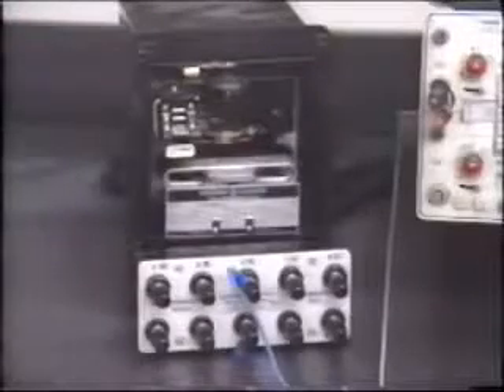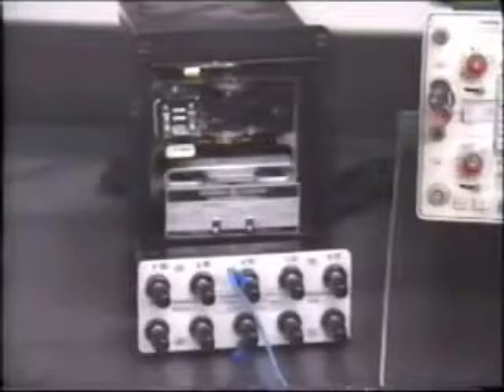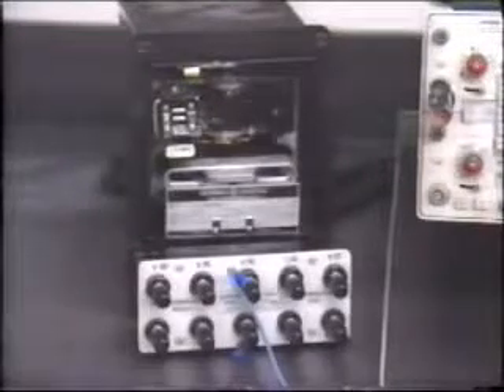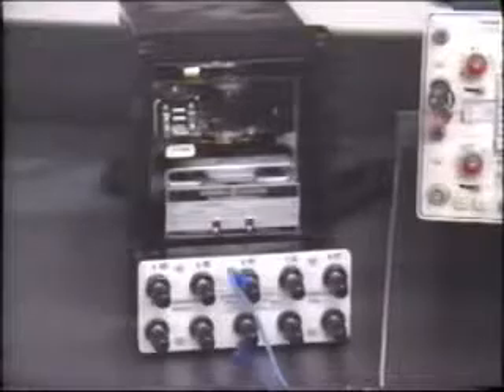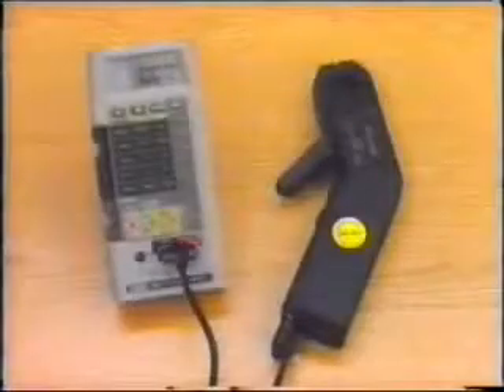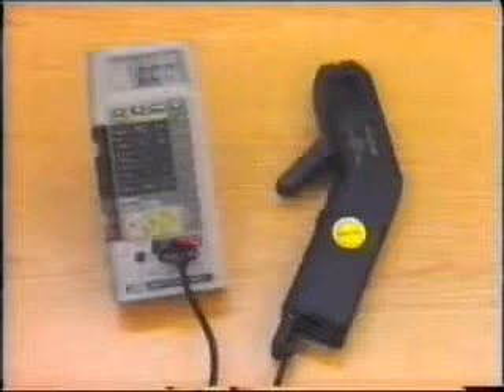In this example, we are testing a time delay over current ground relay. We find that the actual time current curve does not follow the manufacturer's instruction book curves. Is the test set distorting the waveform, or is the relay itself in trouble? If only we could view the current waveform to find out. Well, we can, using a Hall effect probe.